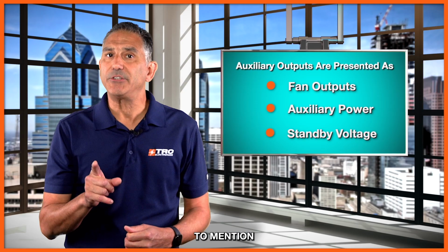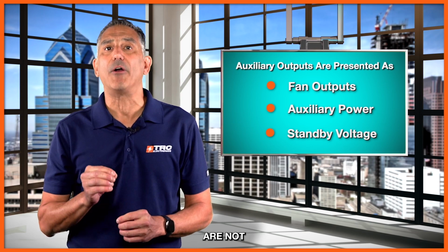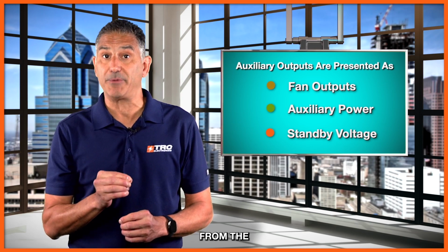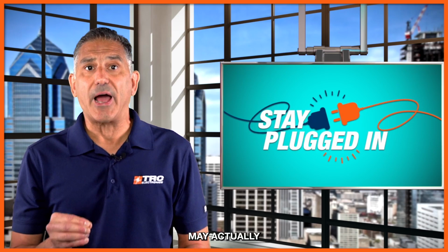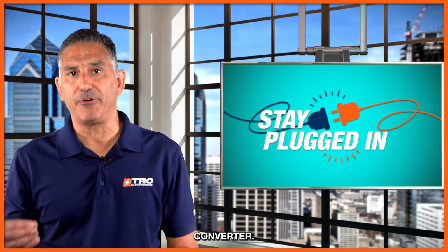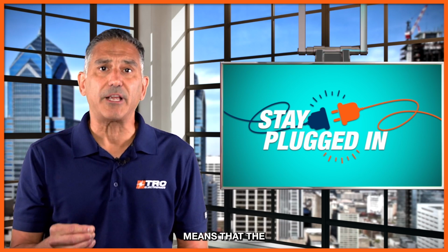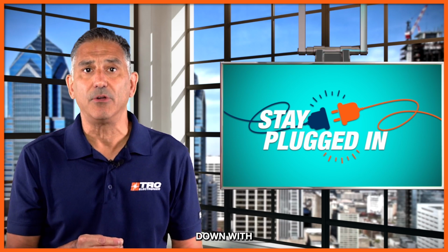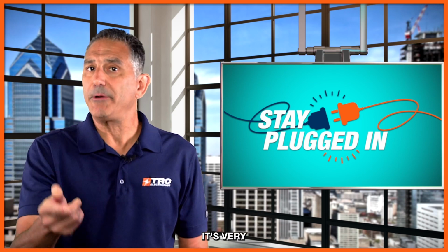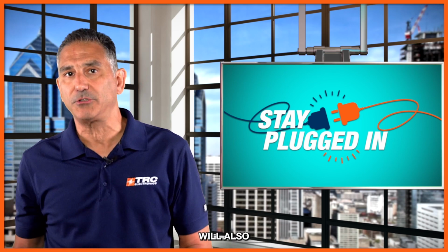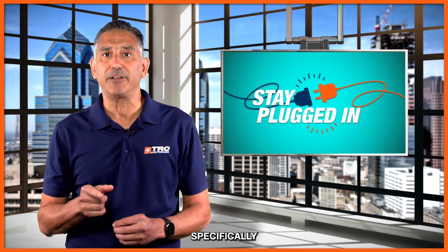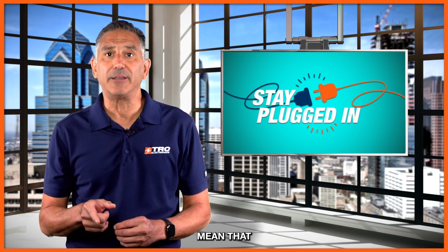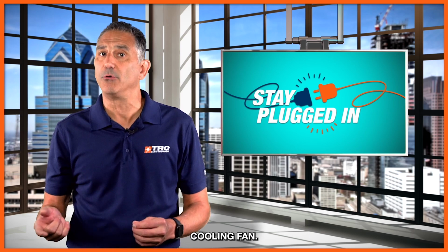It's important to mention that some of these outputs are not exactly independent from the main output. For example, a fan output may actually be running off the main converter. This means that if the main converter is powered down with a remote signal, it's very possible that the fan output will also be powered down. Now, power supply data sheets that specify fan outputs mean that the output is dedicated for a cooling fan.